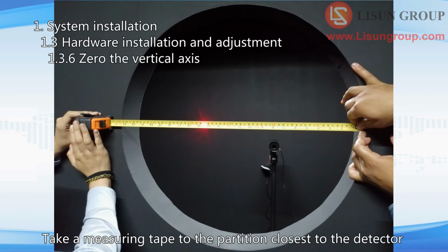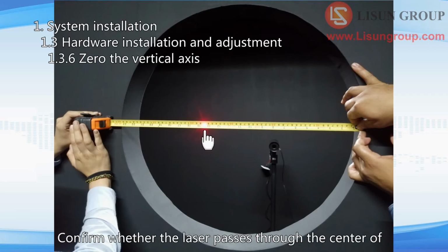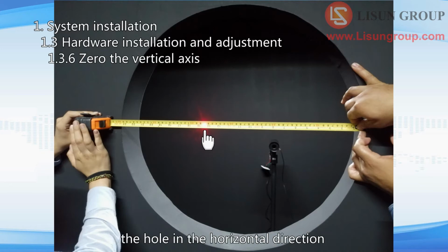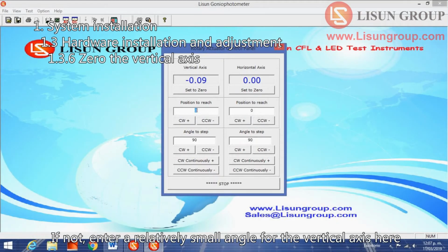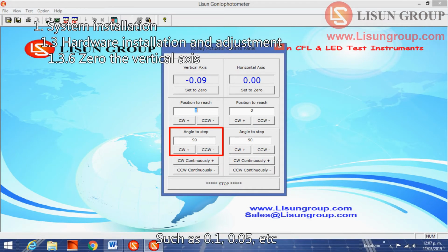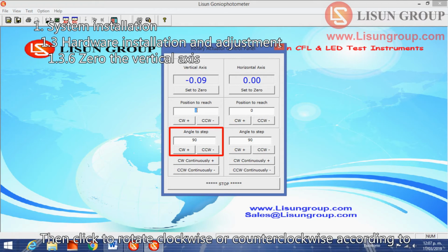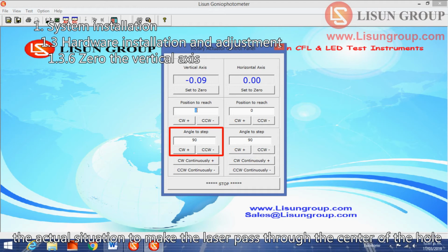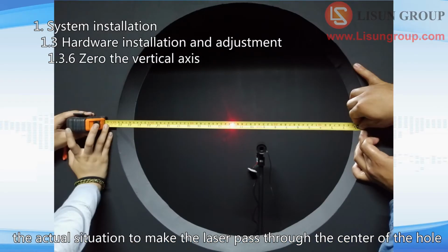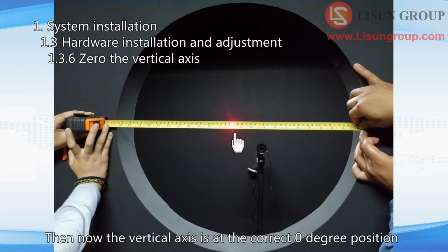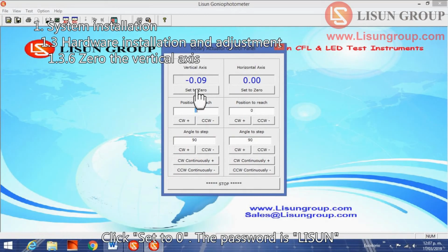Take a measuring tape to the partition closest to the detector. Confirm whether the laser passes through the center of the hole in the horizontal direction. If not, enter a relatively small angle for the vertical axis here, such as 0.1, 0.05, etc. Then click to rotate clockwise or counterclockwise according to the actual situation to make the laser pass through the center of the hole. Then now the vertical axis is at the correct 0 degree position. Click Set to 0. The password is LISUN.